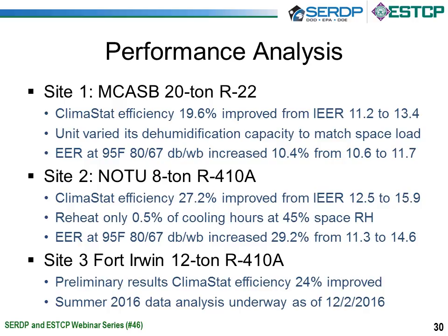At Site 2, the efficiency with the ClimaStat improved from 12.5 to 15.9, so 27% improvement. Key here is that reheat was only used at 0.5% of the cooling hours, and this was maintaining a 45% space relative humidity level. This was a laboratory environment that had a very tight requirement for temperature and humidity, and the existing previous unit used a lot of reheat to maintain this level of humidity, whereas the ClimaStat unit used very little reheat. And the efficiency rating here at 27.2% does not count the reheat savings. It'd be much, much higher if we counted that. This is just looking at the cooling efficiency.